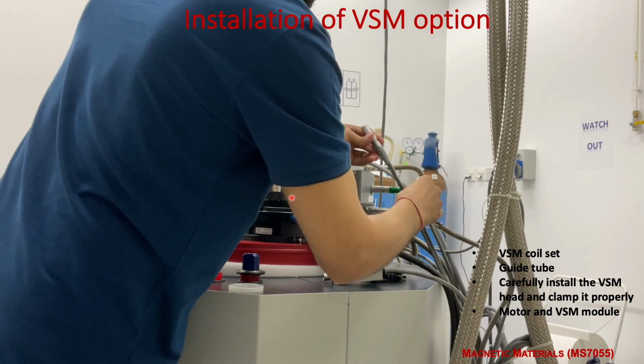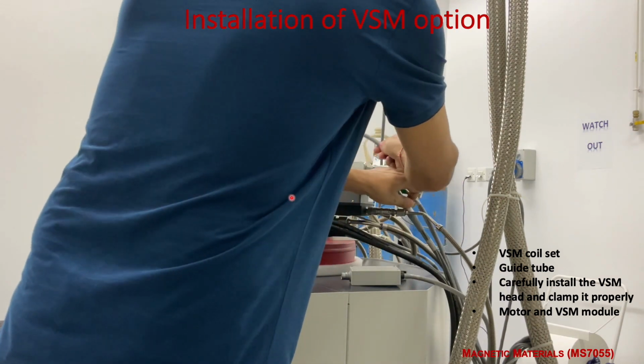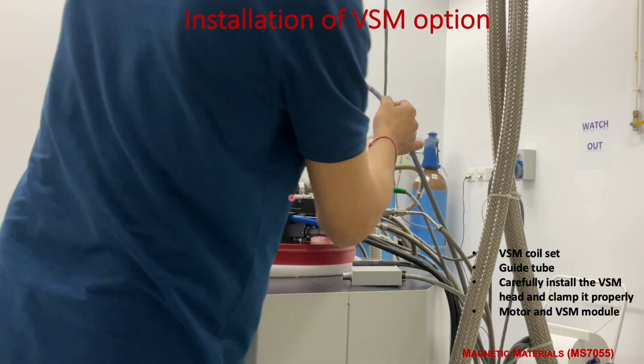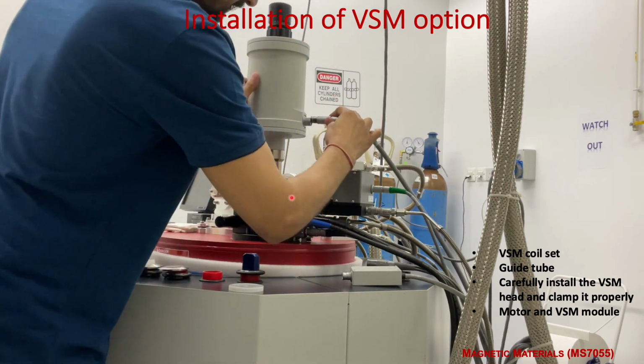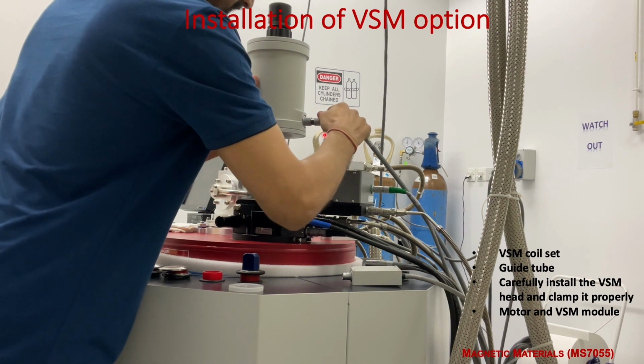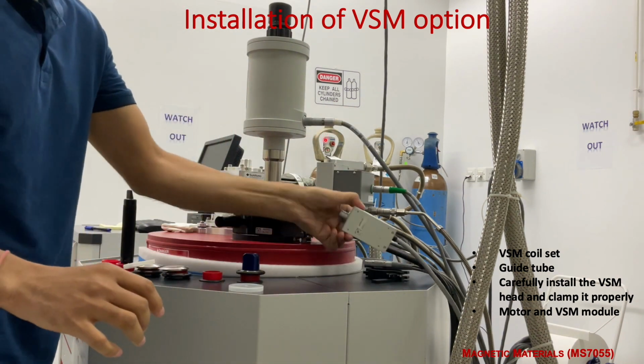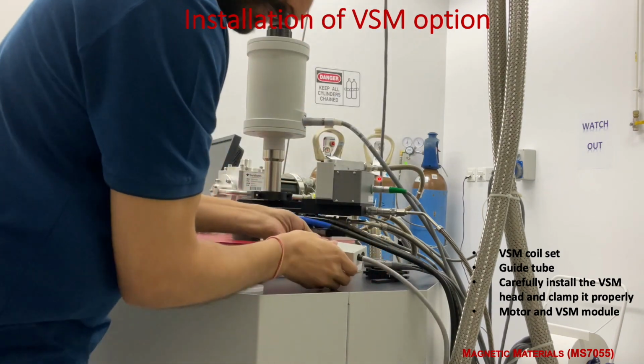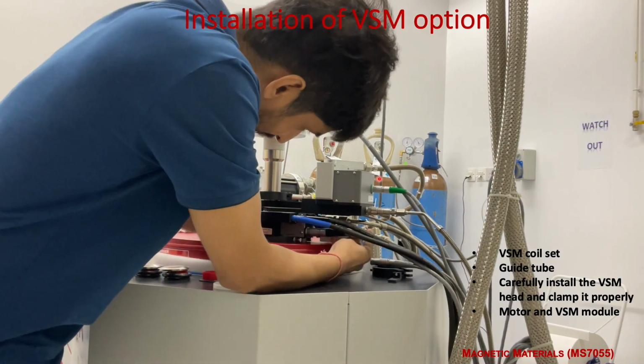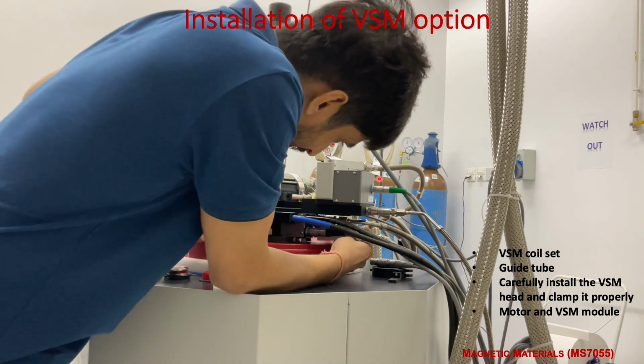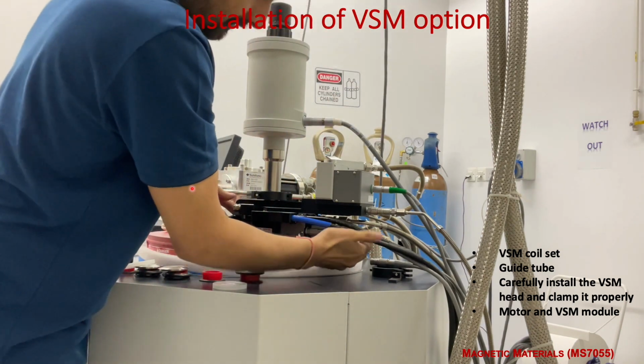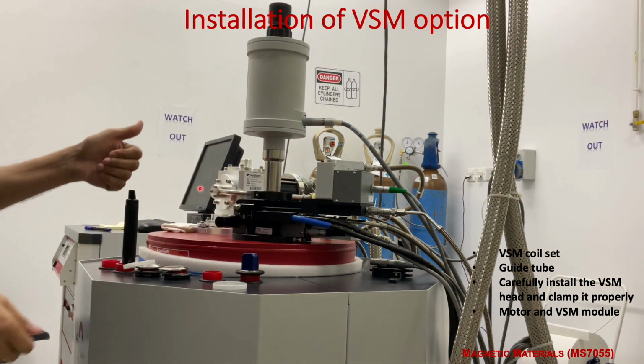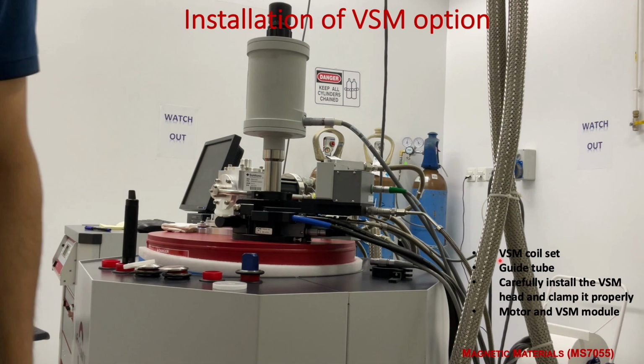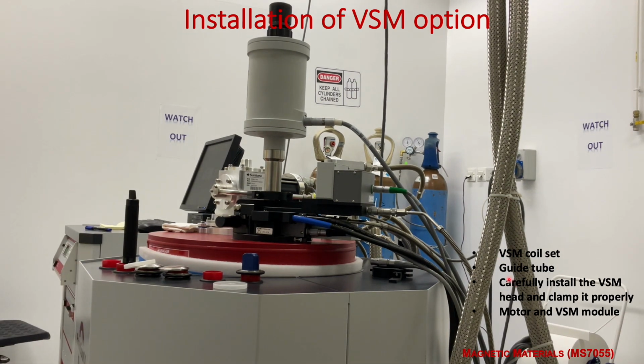So now I'm attaching the motor module first. There are so many cables here. We have tagged the names there. So I have attached this motor module, and now I'm attaching the VSM module. Yeah, so now this is done. Now we have installed the VSM coil set, guide tube, and the VSM head, as well as the motor and VSM modules.